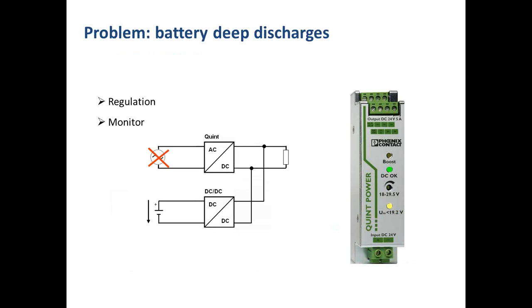Regulation. It's a very common requirement for battery applications. As you know, as the battery voltage drops, the field device can be influenced at some voltage. A DC to DC will accept the dropping input voltage from the battery and provide a regulated output voltage to the field device. During the gradual drop of the battery voltage, the DC to DC is monitoring the situation, looking for 80% of the nominal input voltage. Once the 80% level is reached, the DC to DC will alarm, letting the control system know that any further drop in battery voltage will lead to a deep discharge situation.